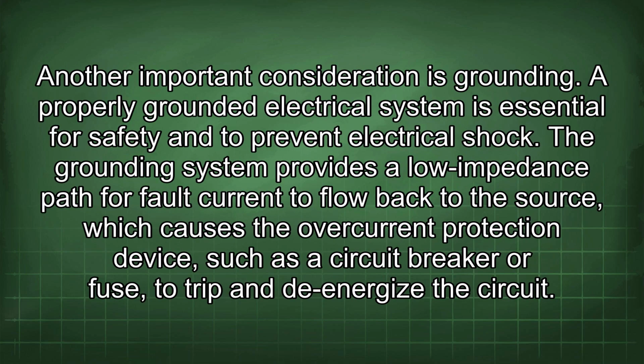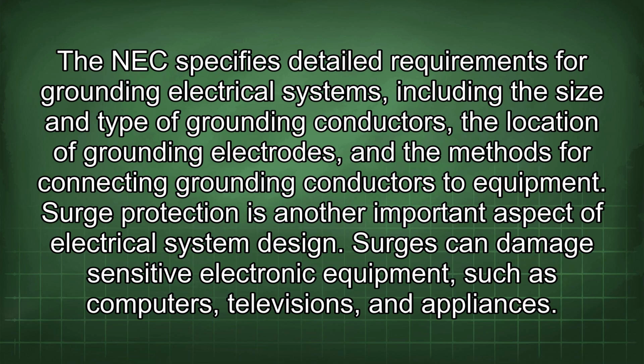Another important consideration is grounding. A properly grounded electrical system is essential for safety and to prevent electrical shock. The grounding system provides a low impedance path for fault current to flow back to the source, which causes the overcurrent protection device, such as a circuit breaker or fuse, to trip and de-energize the circuit. The NEC specifies detailed requirements for grounding electrical systems, including the size and type of grounding conductors, the location of grounding electrodes, and the methods for connecting grounding conductors to equipment.